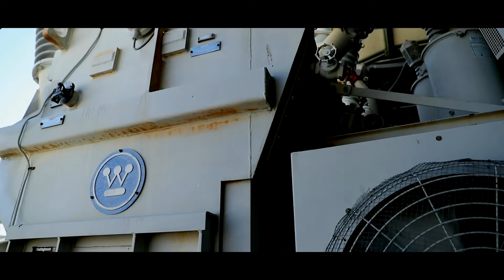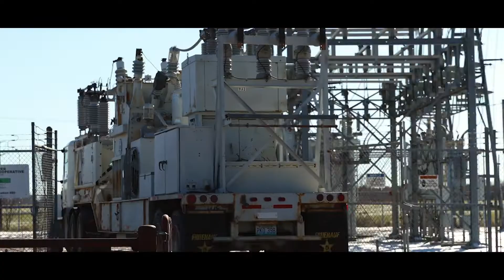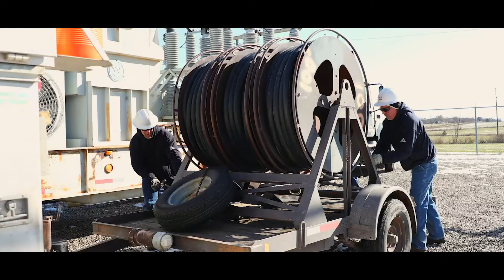So Jeff Boland got the DGA analysis on our oil test back. We have confirmed high gas in the LTC on the transformer at Montreal. They're sending us up here today to bring the mobile in to install for tomorrow so we can get that transformer out of service and figure out what the issue is. The gas is high in the LTC compartment. It's not anything out of the norm, but with this one, the LTC is actually out of service and being run by regulators, so we shouldn't have many high gases in that compartment at all.